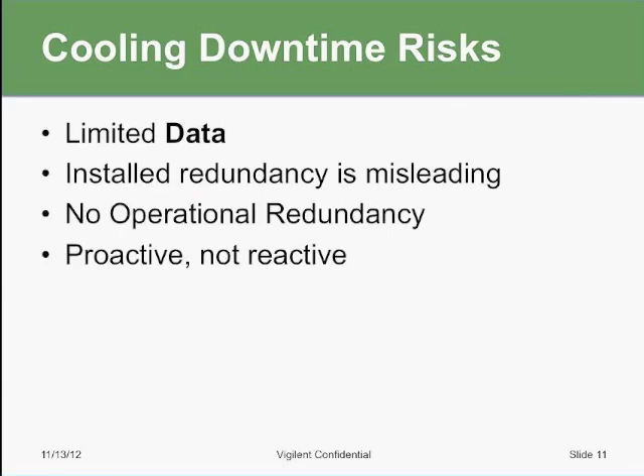And so how do you know as a facility operator if you have downtime risk in your facility? It really starts with data. If you're driving blind, you just have no clue as to how your facility is actually operating. So that's data on the cooling, the thermal side, so a granular amount of data on where the rack inlet temperatures are, but then also about the cooling units themselves to understand their performance and efficiency. And this data can begin to give you visibility into the operational redundancy and operational dynamics of your facility. And again, the installed redundancy is misleading. It's not what you have installed or how much you have installed, but how you're operating that equipment.